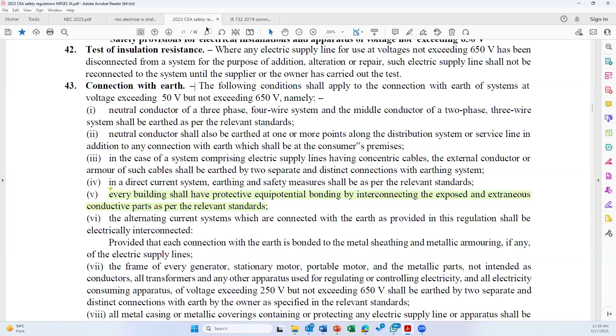For example, this is connection with the Earth, Regulation 43. You can see here, every building shall have protective equipotential bonding by interconnecting the exposed and extraneous conductive parts as per the relevant standard. Here, NEC has made very clear how you should make equipotential bonding, and it has very clearly written that this requirement has nothing to do with the earth pit. It has something to do with the basic idea: electric shock is not because of potential, it's because of potential difference. In your building, you have a lot of conductive parts. You interconnect or bond all the conductive parts. As a result, no potential difference exists, and as a result, there is no shock.